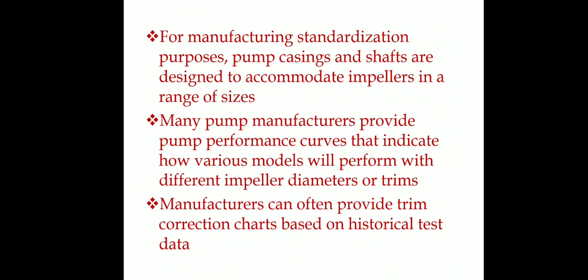Manufacturers also provide pump performance curves. These indicate how various models will perform with different impeller diameters or trims. When we have the performance analysis curves, we have to optimize and carry out the impeller trimming accordingly.